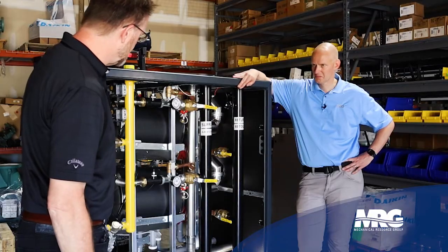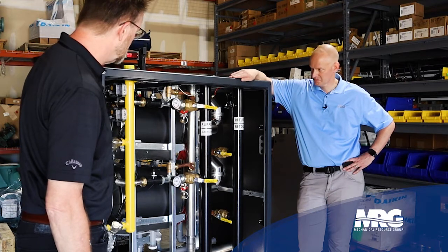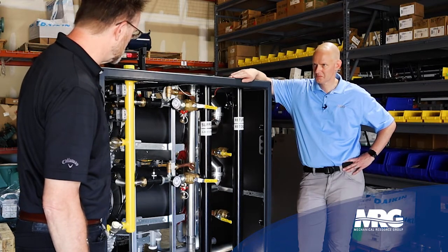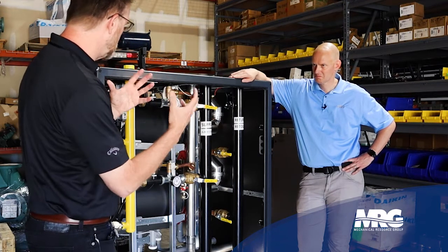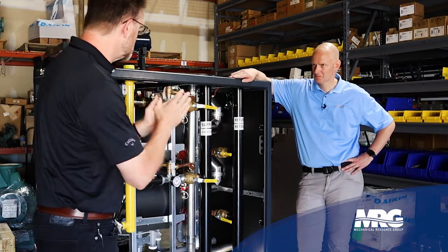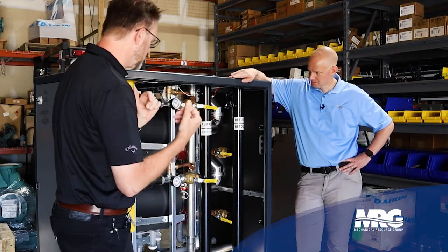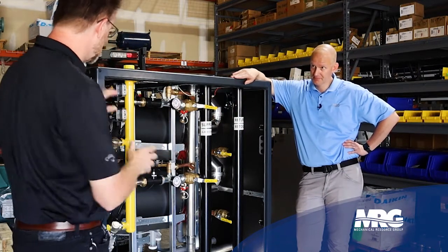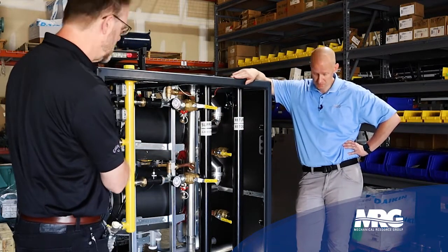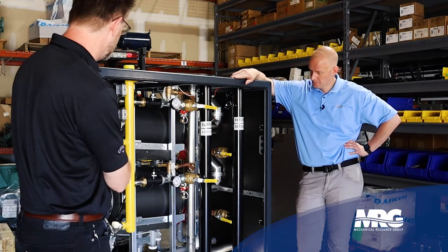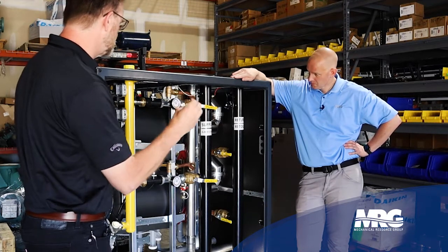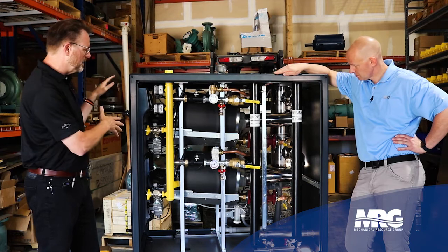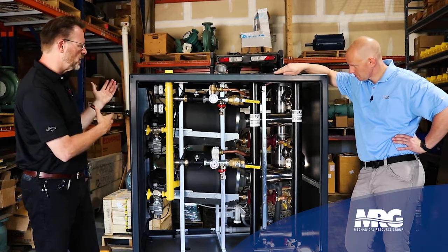We also had a low water cutoff challenge where the system got some air in it, and it was detected by the low water cutoff because it became airbound, since there was air where there was not water. This here's our low water cutoff, the one that we referenced. We talked about the fact that each of the helix heat engines has its own low water cutoff, and to evade the collection of air, we have automatic air vents near those low water cutoffs.